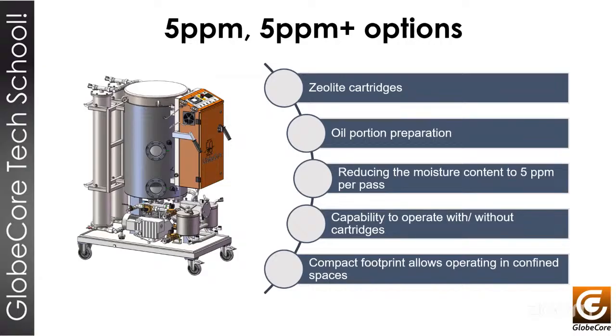In order to accomplish this, a small-size solid cartridge was specifically developed. You can see here on the left hand of the machine, we have two cartridges of zeolite, and this zeolite is the element that helps you to reach really low levels of moisture inside the oil.